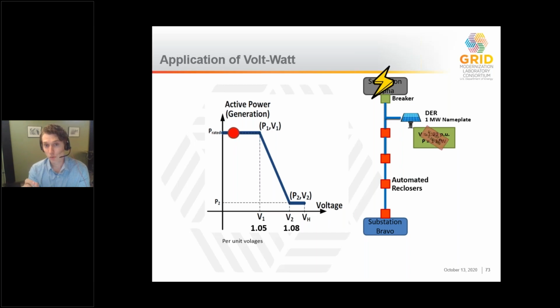Next slide, please. We have the potential for a high voltage. So let's just assume that the voltage goes up to 107% of the nominal voltage. What we would see with this Volt-Watt activated is an automatic adjustment of the power output from the DER to drop to a lower level to try to help contribute to mitigating voltage rise in this case. So this function could be very helpful for these abnormal configurations of the system that we haven't studied during interconnection analyses in order to provide some sort of backup soft shutdown function. Next slide, please.